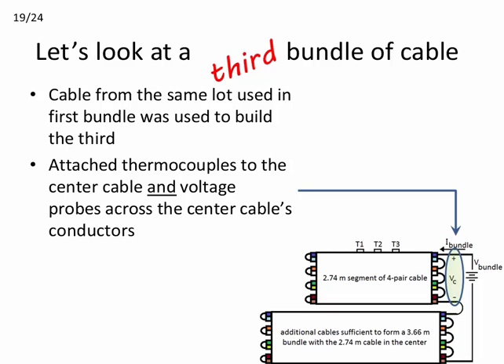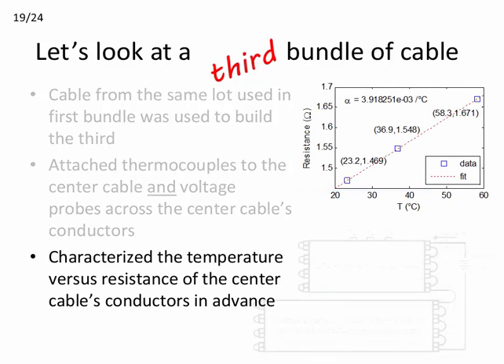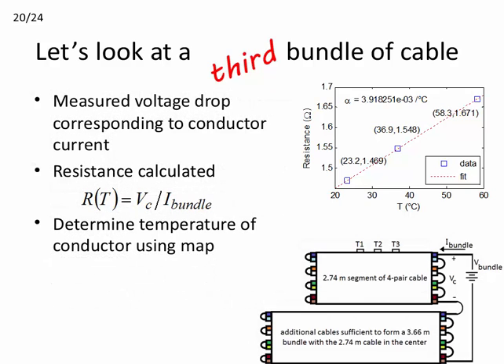To do this, we built a third cable bundle. But before constructing the bundle, we connected the conductors in what would be the center cable in series and outfitted this new composite conductor with low resistance leads. This cable was placed in an oven, and the resistance versus oven temperature was mapped. At this point, we've got a relationship between the resistance of the conductors in the center cable and their temperature. We then used this mapped cable as the center cable in a 91 cable bundle. The leads used to evaluate the resistance in the oven now functioned as voltage probes with which we could determine a voltage drop for a given current. The voltage drop and current allowed for us to relate the resistance of the center cable's conductors to their temperature via the earlier generated map. In short, we're now able to measure the temperature of the conductors in the center cable.